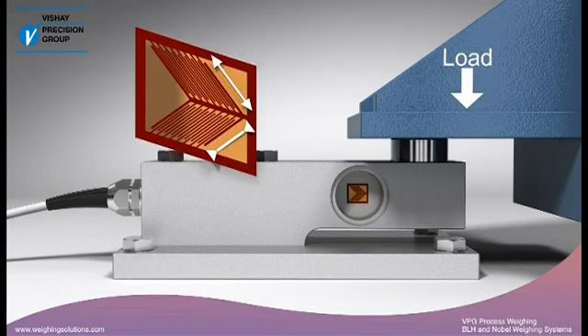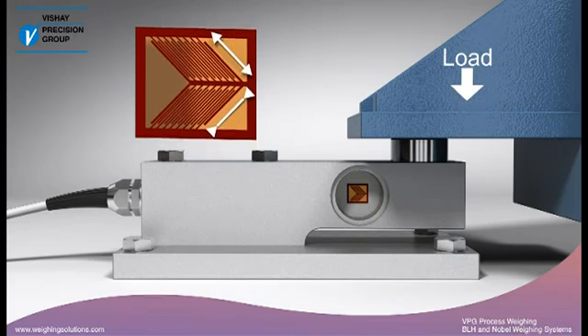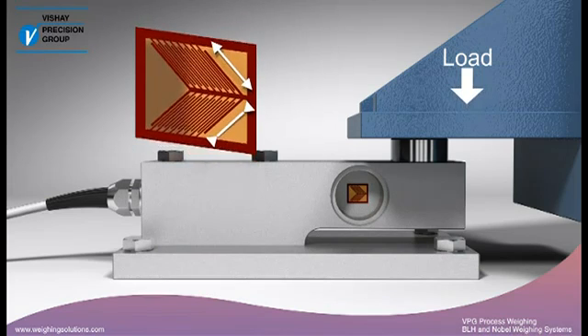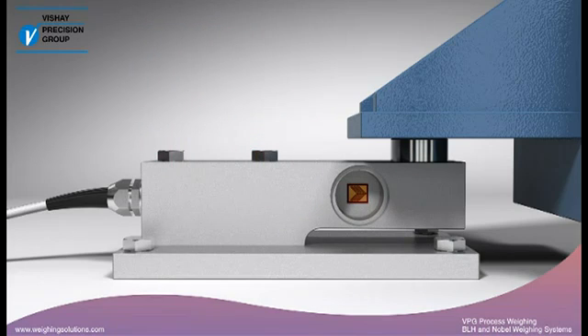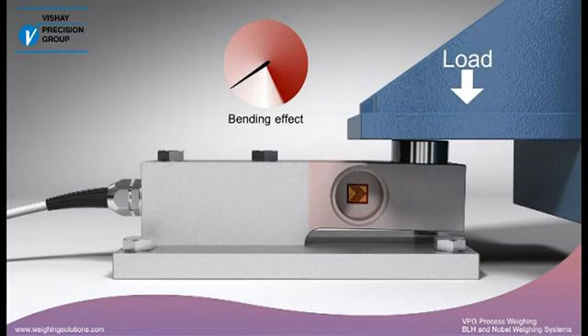They are stretched or compressed as the web is sheared by the load. The gauges are designed to measure the shear strains in the web. In a simple shear beam, there are also bending strains present which contribute to the output.